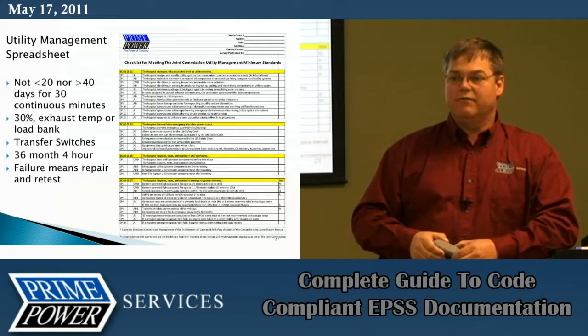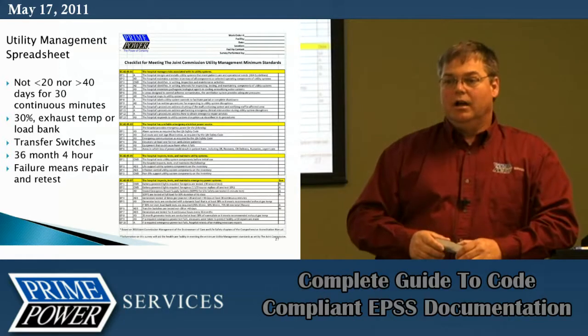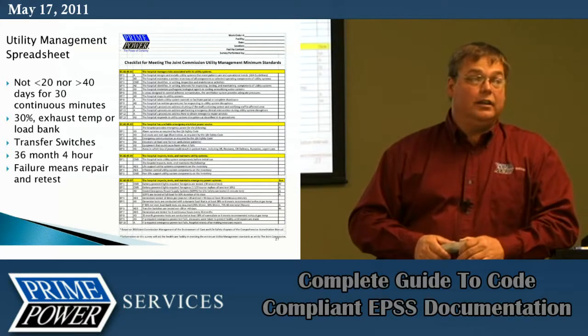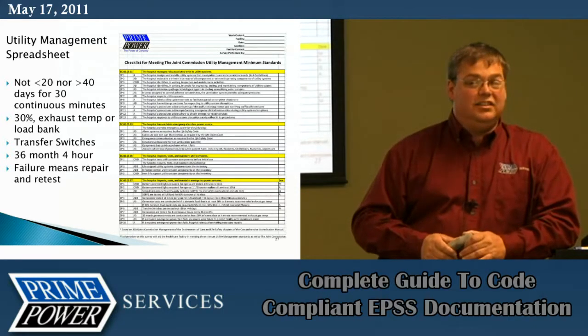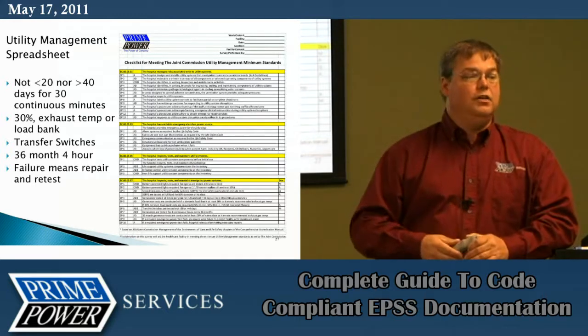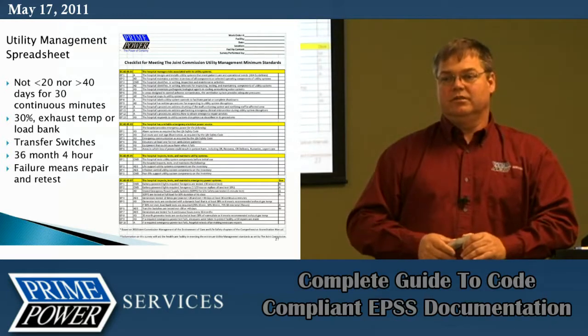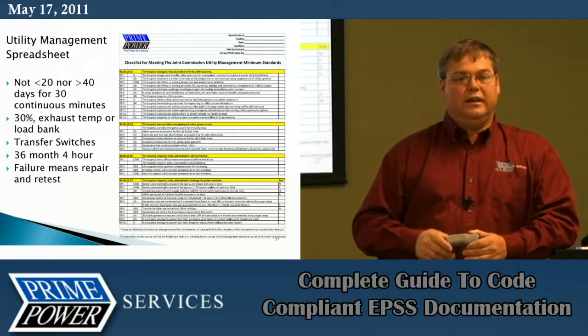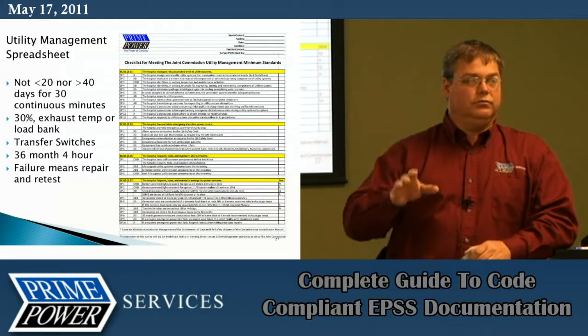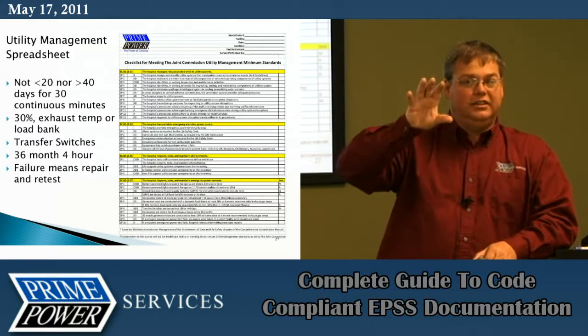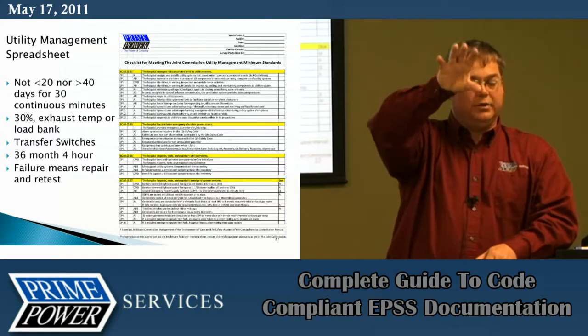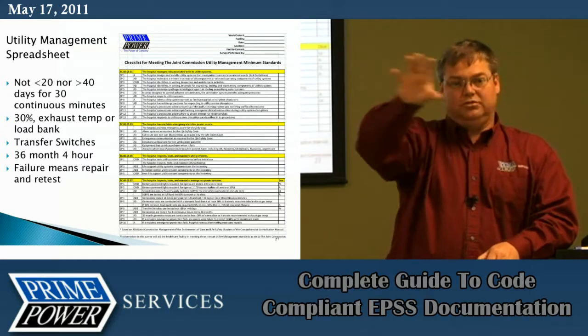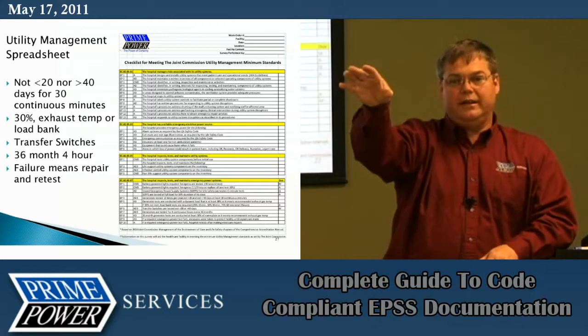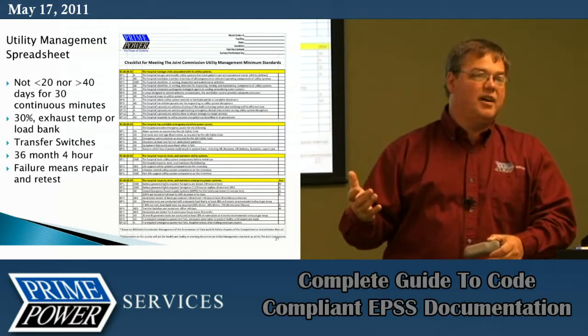And Joint Commission will look for that during your documentation as well. For you non-healthcare guys, it's still a great idea. You're not testing the component of starting that generator if you don't rotate your switches. So just every month, it's very simple. Take a little magnet of some type and stick it on the door of the transfer switch or the cabinet of the transfer switch. Start here, and next month rotate it to the next one, rotate it to the next one. At least it gives you an opportunity.